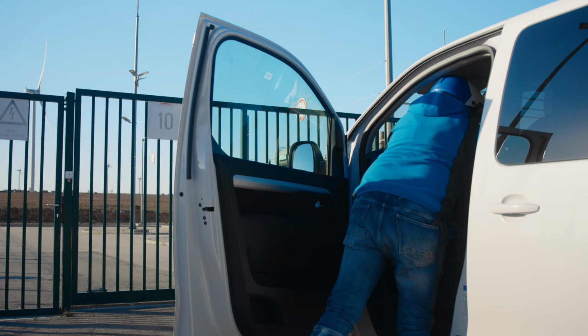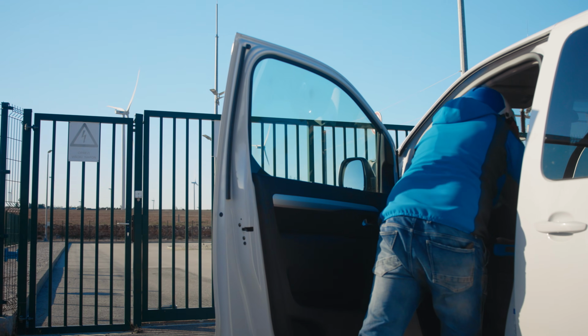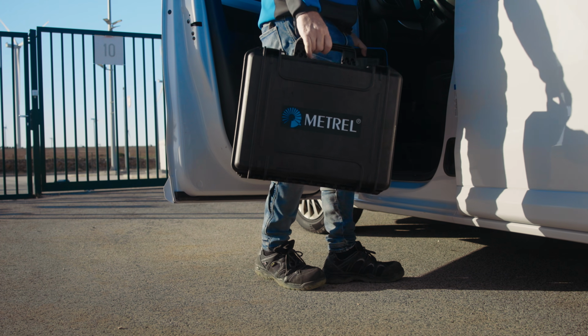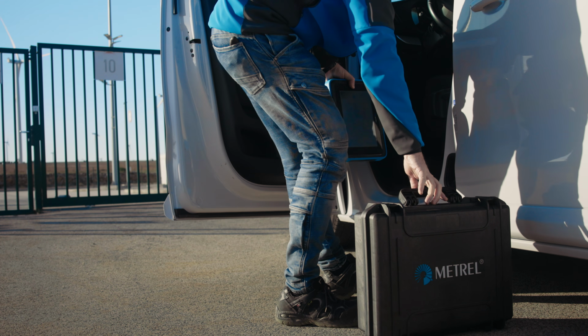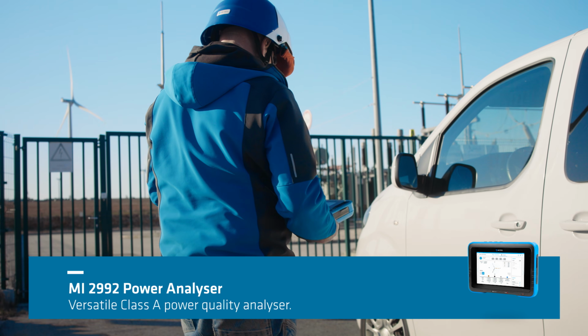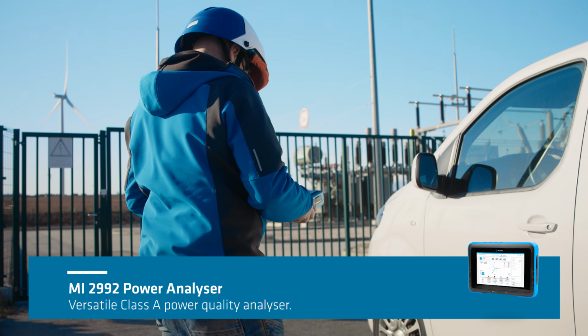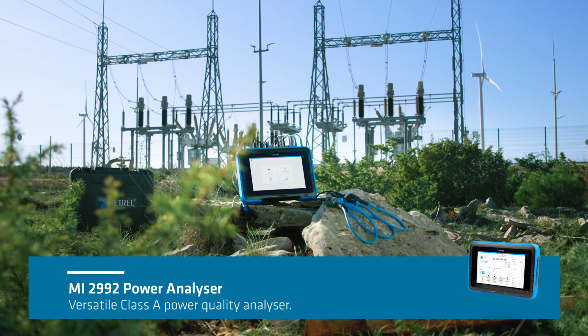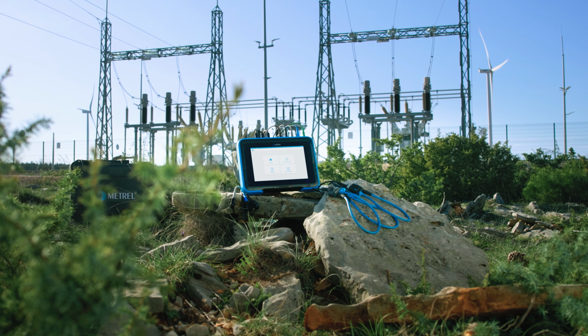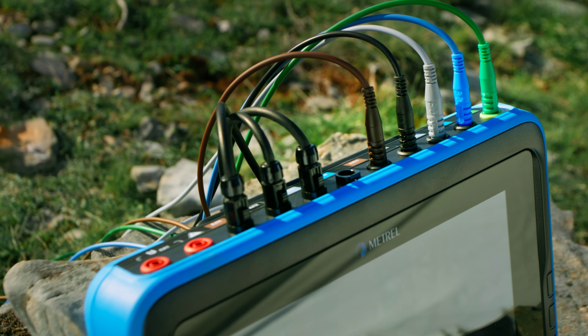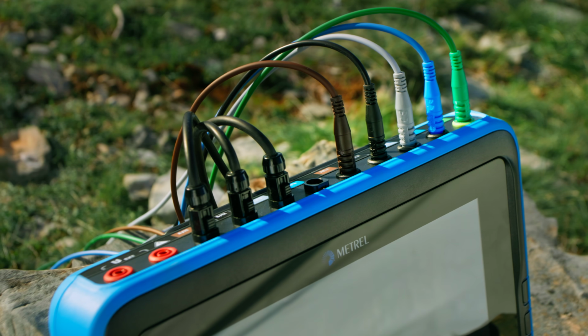But testing doesn't stop there. Substations connected to wind farms must also be thoroughly assessed. This includes identifying and resolving any power quality issues that could degrade the transfer of energy into the distribution network, using the MI 2992 Power Analyzer or any other Metrel Class A power quality analyzer.